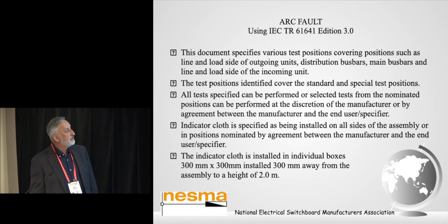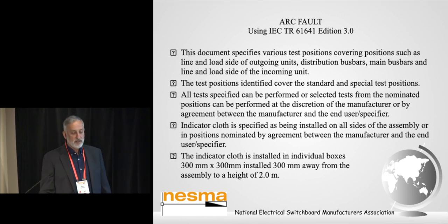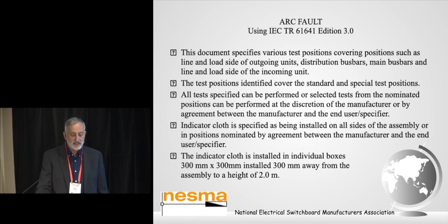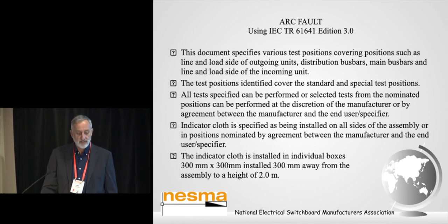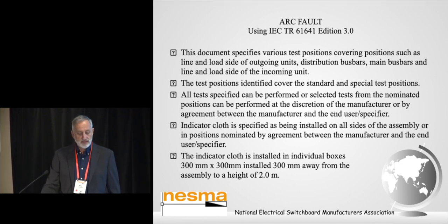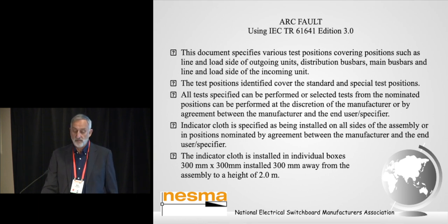The arcing fault using the 61641 edition 3, this document goes a bit further and specifies various test positions such as the line and load side of outgoing units, distribution bars, main bars and line and load side of the incoming unit. The test positions identified cover the standard and special test positions. All tests specified can be performed or selected tests from the nominated points or can be performed at the discretion of the manufacturer or by agreement between the end user and the specifier.